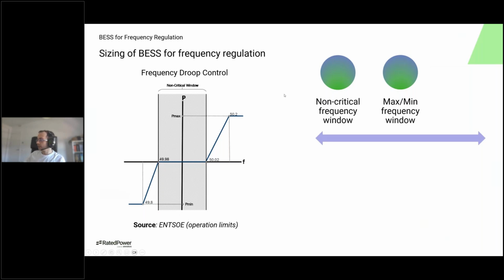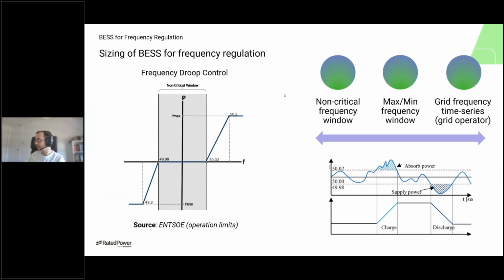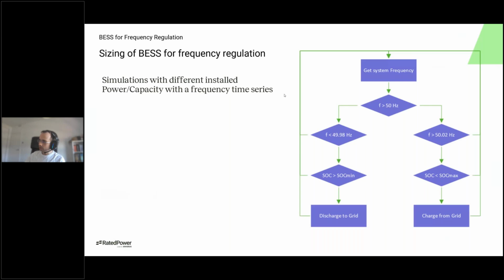ENTSOE. And finally, we know our curve of operation, and we need a time series, a grid frequency time series provided by the grid operator. This is in order to simulate a real case scenario and check the capability of our battery system. So the idea would be, given this information, we will be able to simulate with different combinations of installed power and capacity using the frequency time series from the grid operator. So it will be very simple.